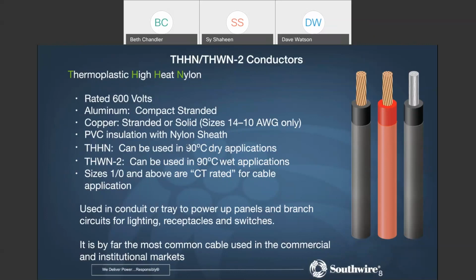The nylon is there to protect the PVC insulation. Its job is really a protection of that. It's not to provide additional electrical capability. In fact, when we do the testing for the electrical parameters of this product, we do it without the nylon sheath. So let's say during the installation process, that nylon sheath or jacket gets damaged and the underlying PVC insulation is not damaged, what does this do to the product? Well, the nylon is there to protect it. The nylon is very abrasion resistant. So when you're pulling it through conduit, it's good about protecting from any abrasion from the conduit walls.